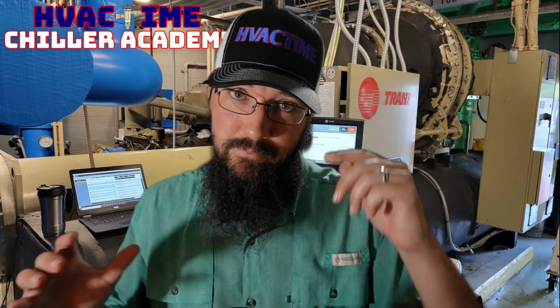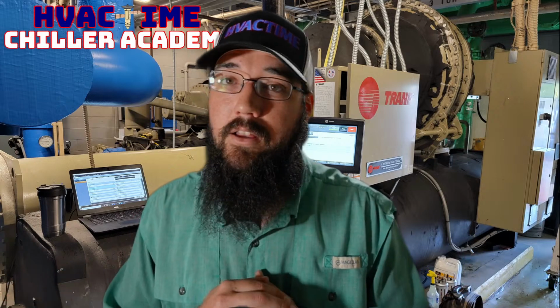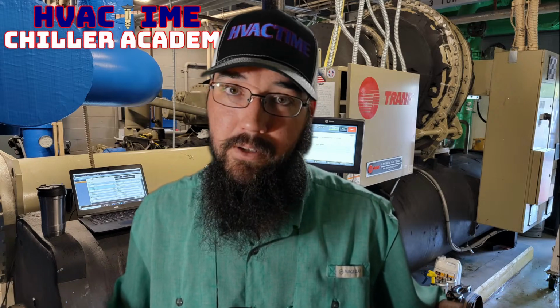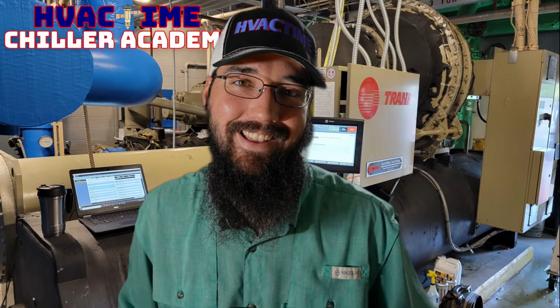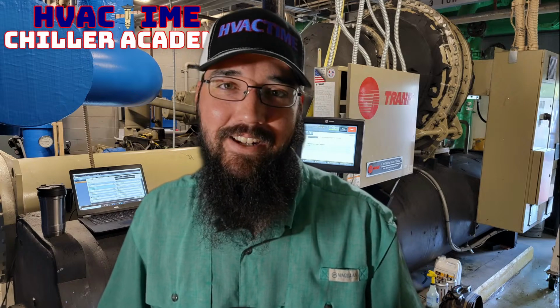Oh yeah, that'll wipe out an impeller in a heartbeat. These impellers are pure aluminum, but they're inside of steel housings, and aluminum gives to steel, if you didn't know. So one good touchdown, if that thrust bearing goes bad or something happens and they don't prevent it, you get one good hard touchdown at 20-something thousand RPM at the horsepower we're running, that impeller is toast. A couple of touchdowns, if not one hard one, and it's shredded. So, yeah, not good.